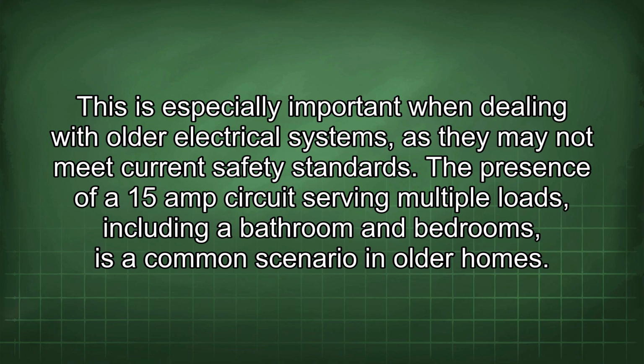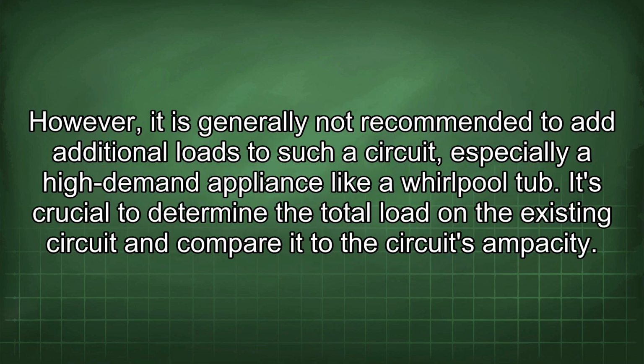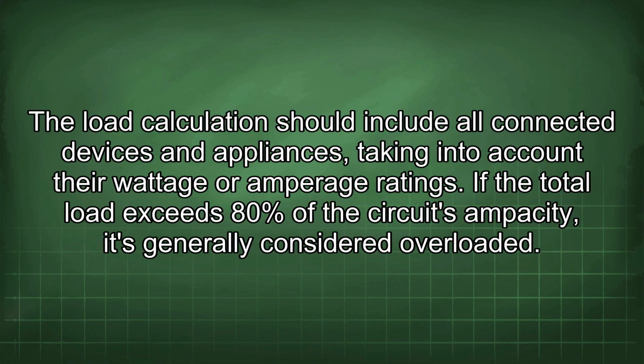The presence of a 15-amp circuit serving multiple loads, including a bathroom and bedrooms, is a common scenario in older homes. However, it is generally not recommended to add additional loads to such a circuit, especially a high-demand appliance like a Whirlpool tub. It's crucial to determine the total load in the existing circuit and compare it to the circuit's ampacity. The load calculation should include all connected devices and appliances, taking into account the wattage or amperage ratings. If the total load exceeds 80% of the circuit's ampacity, it's generally considered overloaded.